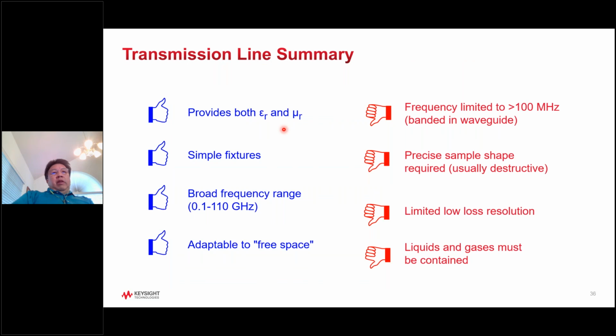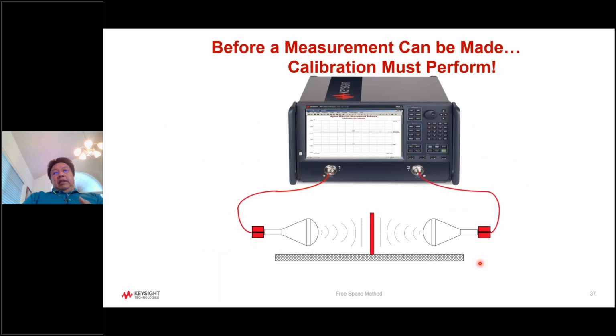So, in summary of the transmission line method, it provides both epsilon and mu, and the fixture is simple, well, I guess depending on your definition, and it provides broad frequency coverage, actually up to 1.1 terahertz. In terms of limitations, because the waveguide is really large at low frequency, the sample is really large, so it may not be practical. It is also limited to somewhat low loss, with measurement resolution limits. I will talk more about that in the next few slides. And if you have a liquid, it's kind of hard, because getting liquid to fit inside a waveguide is difficult. So next is the transmission line method called free space.